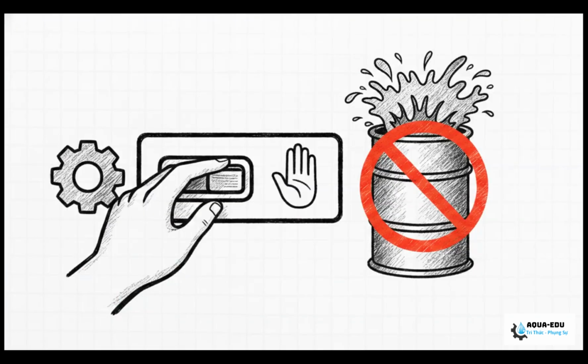Listen up, guys, because this is literally our highest priority. The absolute most critical thing I need you to do in the first 2 hours of a failure is switch the dosing system to manual immediately. Never, ever leave it on auto if you even suspect the sensor is faulty. You are going to manually adjust that dosing based entirely on your handheld readings. Make sure you tag the SCADA screen so the control room knows what's up, and grab a lab sample for a true baseline. We have to prevent a chemical overdose that could completely crash our biological basin.